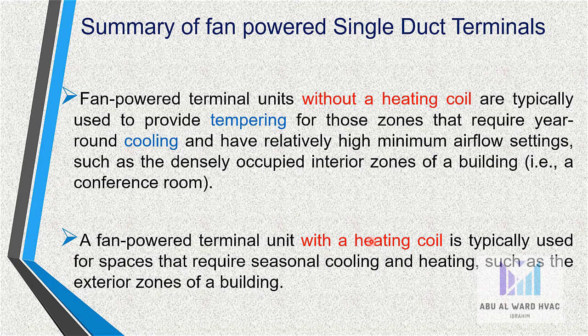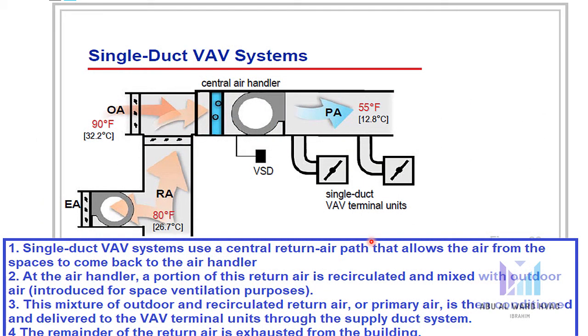A fan powered terminal unit with a heating coil is typically used for spaces that require seasonal cooling and heating, such as the exterior zones of a building. In a single duct VAV system, a central return airflow allows air from the spaces to come back to the air handler. At the air handler, a portion of this return air is recirculated and mixed with outdoor air introduced for space ventilation purposes. This mixture of outdoor and recirculated return air — or primary air — is then conditioned and delivered to the VAV terminal unit through the supply duct system. The remainder of the return air is exhausted from the building.